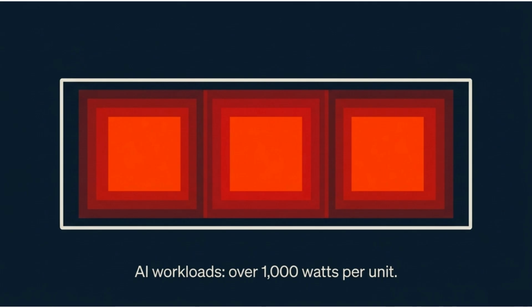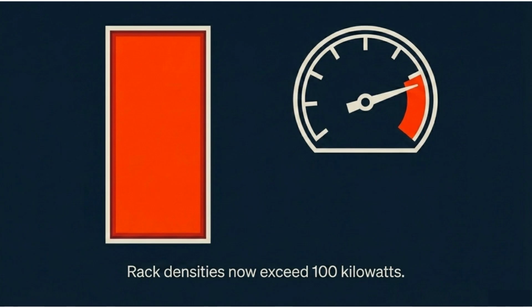The new chips powering AI are absolute beasts. A single processing unit can draw over 1,000 watts. Imagine running an industrial hairdryer on maximum heat, 24/7, inside a tiny metal box. When you stack dozens of these super hot chips together into a single server rack, the heat density goes off the charts. We are now seeing racks that push well past 100 kilowatts of power.